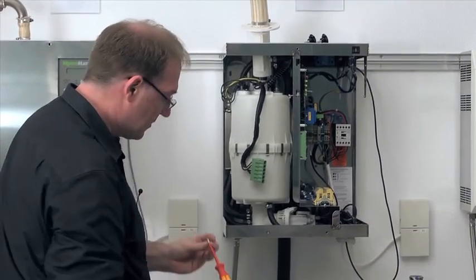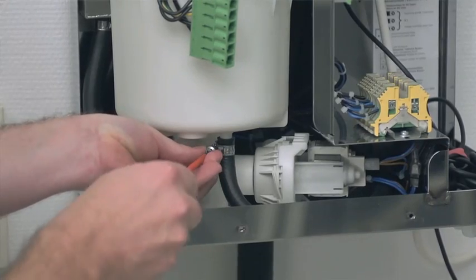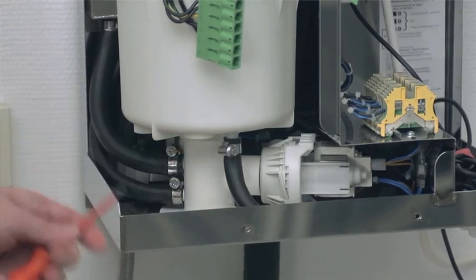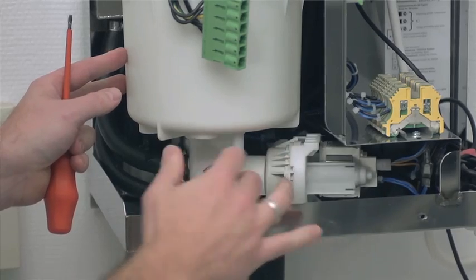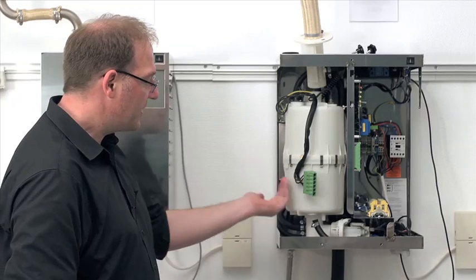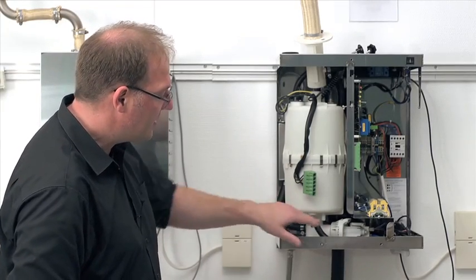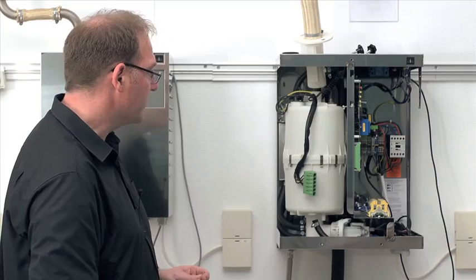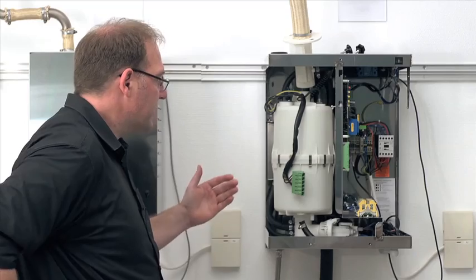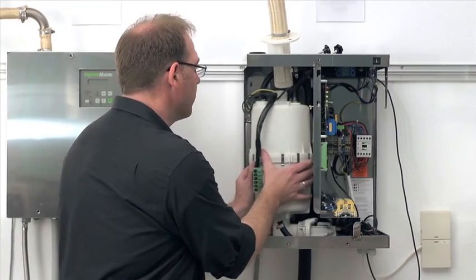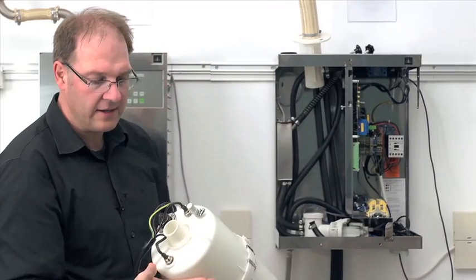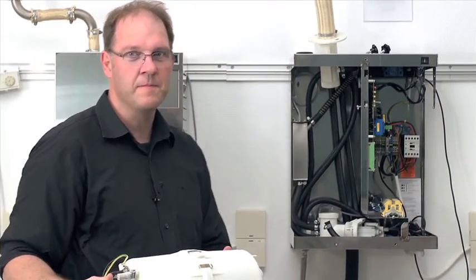And then next, down here, we have a little connecting hose. These units come standard with a SuperFlush flushing device that we have installed. This SuperFlush flushing device assists by enabling an increased discharge of mineral deposits during those times when the blowdown pump is active. After I have disconnected that hose too, I can dismantle the cylinder and lift it out. Now I have it unhooked and in my hands, and I can carry out the maintenance on the cylinder.